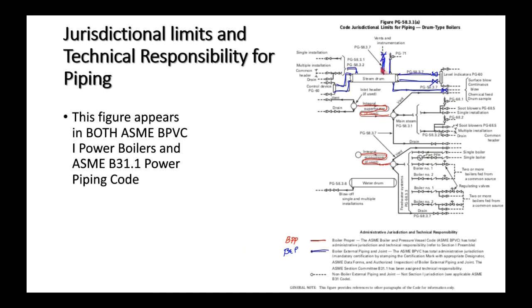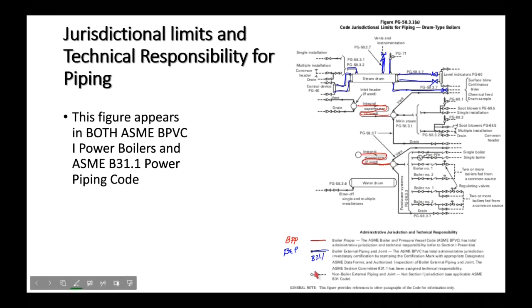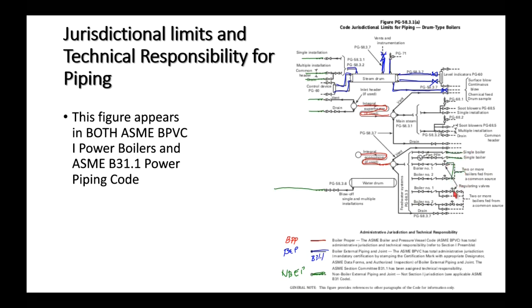Boiler external piping is under B31.1. Non-boiler external piping is the stuff we think about in power plants — blow-off lines, drains, vents from superheaters, main steam lines, feed water lines, and bottom blow-off. This is the big majority of what power engineers deal with, and it's all B31.1.